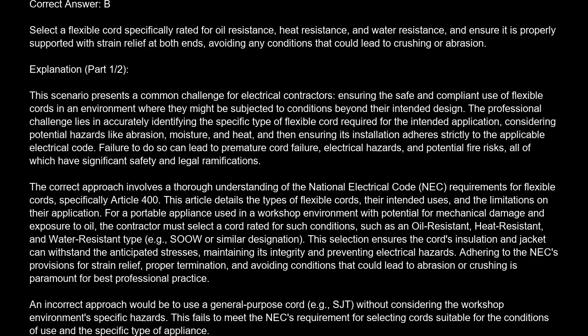The correct approach involves a thorough understanding of the National Electrical Code, NEC, requirements for flexible cords, specifically Article 400. This article details the types of flexible cords, their intended uses, and the limitations on their application. For a portable appliance used in a workshop environment with potential for mechanical damage and exposure to oil, the contractor must select a cord rated for such conditions, such as an oil-resistant, heat-resistant, and water-resistant type, SOOW or similar designation. This selection ensures the cord's insulation and jacket can withstand the anticipated stresses, maintaining its integrity and preventing electrical hazards. Adhering to the NEC's provisions for strain relief, proper termination, and avoiding conditions that could lead to abrasion or crushing is paramount for best professional practice.